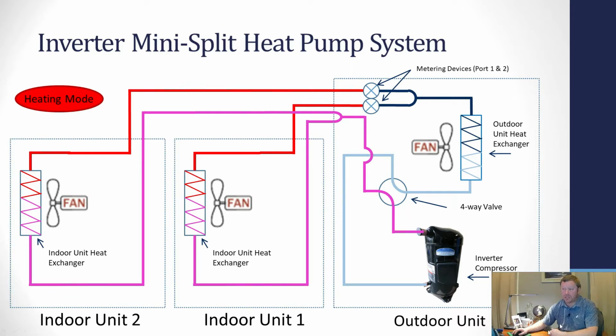You can see in this chart here, when your hot gas comes off the compressor and it goes to your indoor units, out of each port there are no valves preventing that hot gas from going to the indoor units. Every single indoor unit gets hot gas anytime the compressor runs. And so even though indoor unit 1 may not want any more hot gas, it's still getting hot gas.